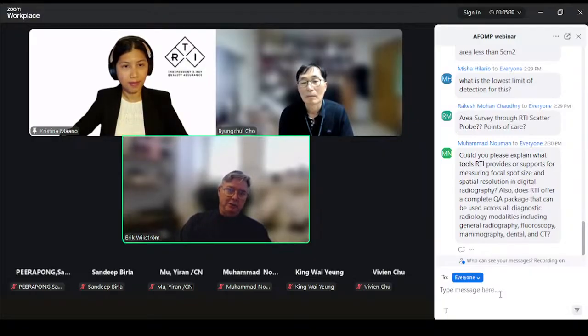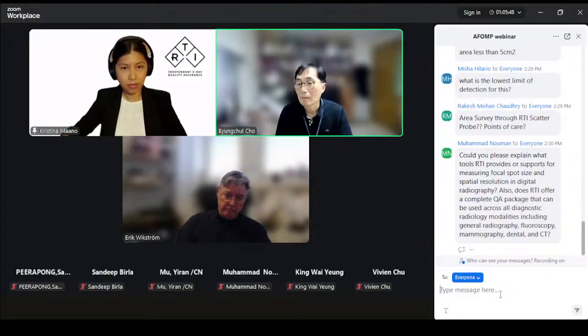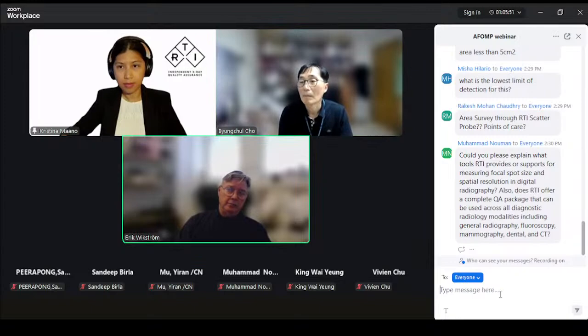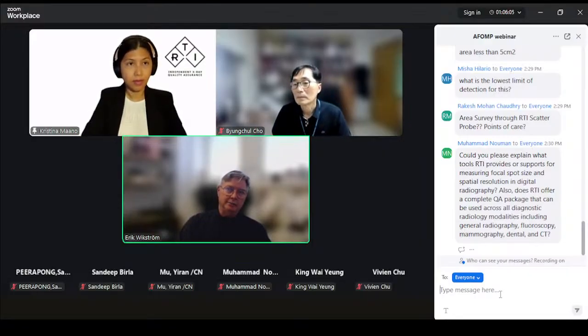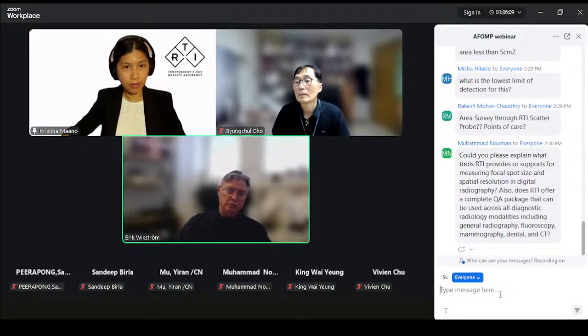And from there, you will then be able to follow and see if there are changes to the background radiation. To get the absolute value is a little bit difficult, since it's not a survey instrument as such. The purpose of it is to monitor and see the additional radiation produced in addition to the background radiation. So if we don't measure the absolute value, then it's a value referenced from the background radiation. But we have seen that it actually does capture changes in background radiation.